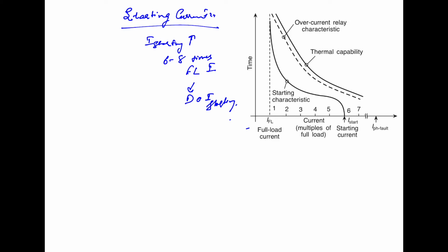Now from this figure you will see the starting current. Here we have the starting characteristics, superimposed on the thermal capability curve of the motor. This is the thermal capability curve of the motor. And from this figure it is observed that the overcurrent relay characteristics must be, this is the overcurrent relay characteristics.